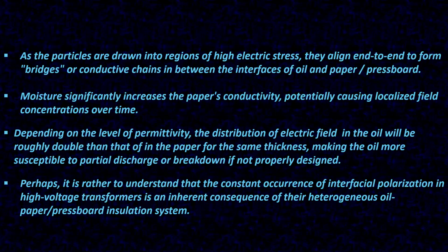As the particles are drawn into regions of high electric stress, they align end to end to form bridges or conductive chains in between the interfaces of oil and paper or pressboard. Moisture significantly increases the paper's conductivity, potentially causing localized field concentrations over time. Depending on the level of permittivity, the distribution of electric field in the oil will be roughly double that of the paper for the same thickness, making the oil more susceptible to partial discharge or breakdown if not properly designed.